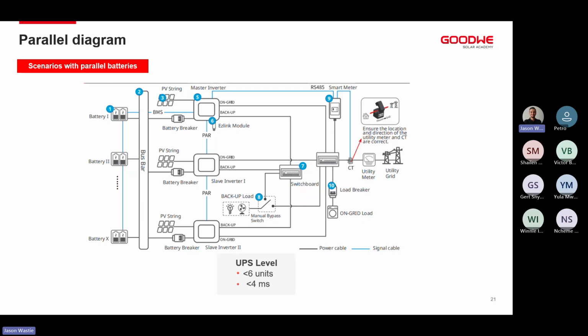So with parallel battery communication, how it works is we'll have one common LV battery bank, connect it to a bus bar, connect all the inverters to that bus bar, and have our communication running from our master battery into the master inverter.